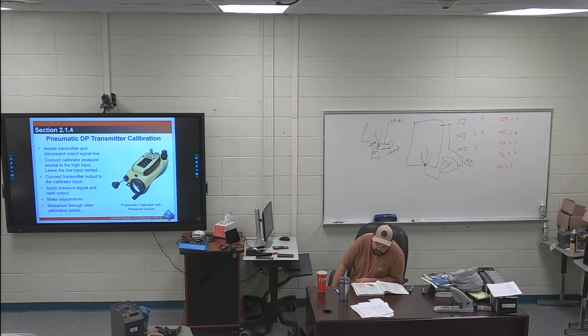This feature allows the technician to set the calibrator for auto step or auto ramp as an input at one location and check or test other parameters at different location as the calibrator steps through the various levels of the source. This is nice when you're working by yourself. You can set this thing up and it'll do 0%, 25%, 50%, 75%, 100%. And you can, because not always the thing you're working on is here and here.